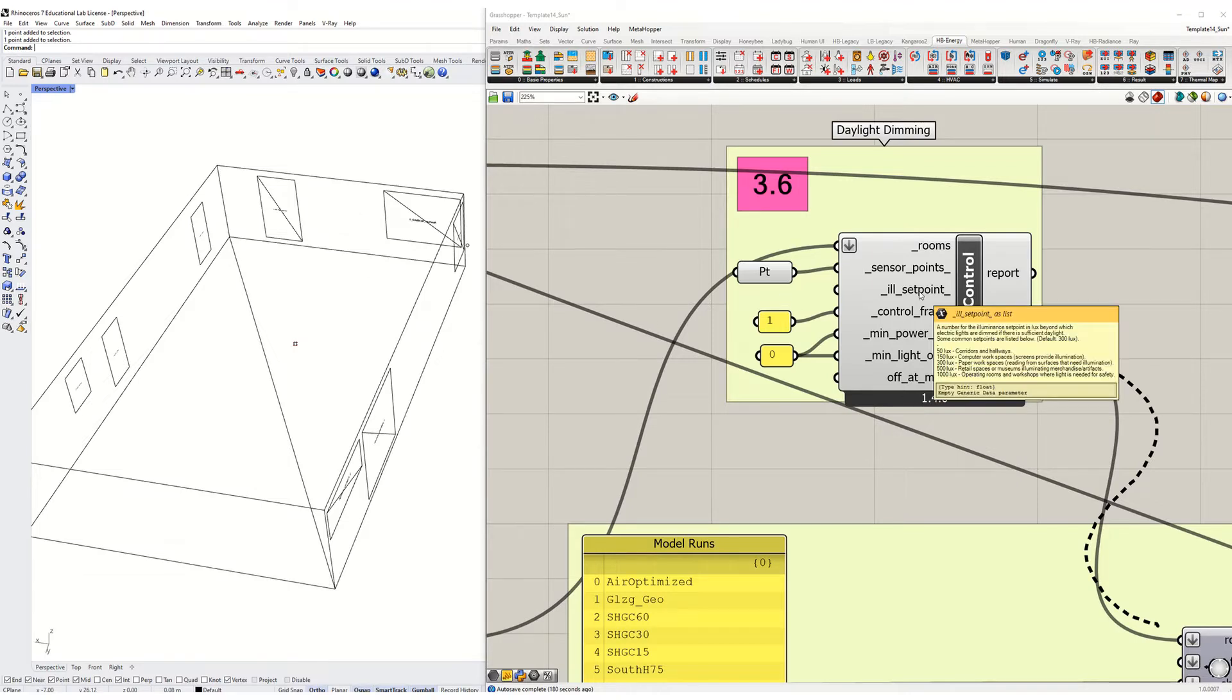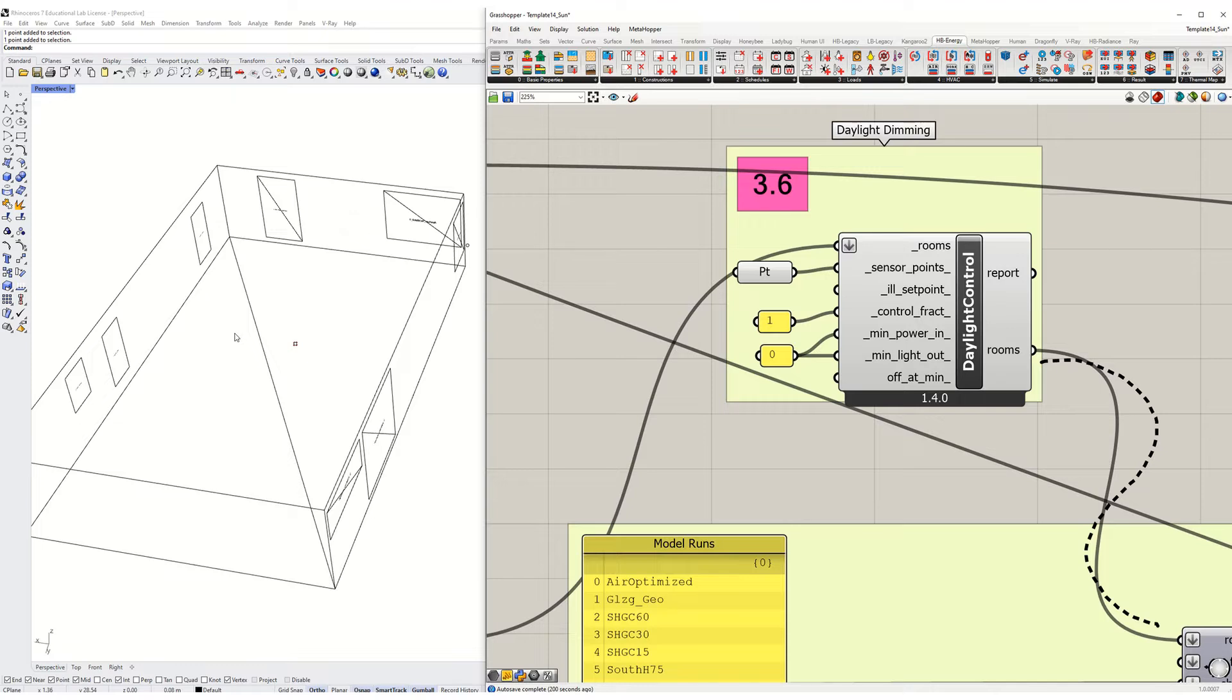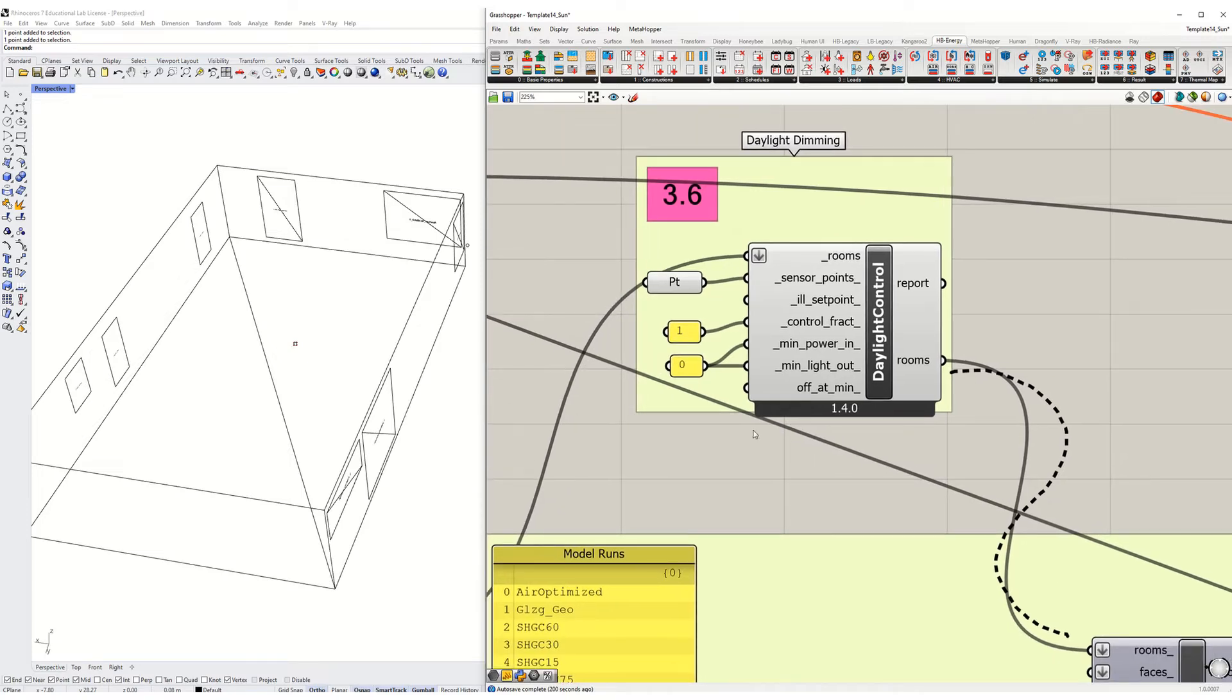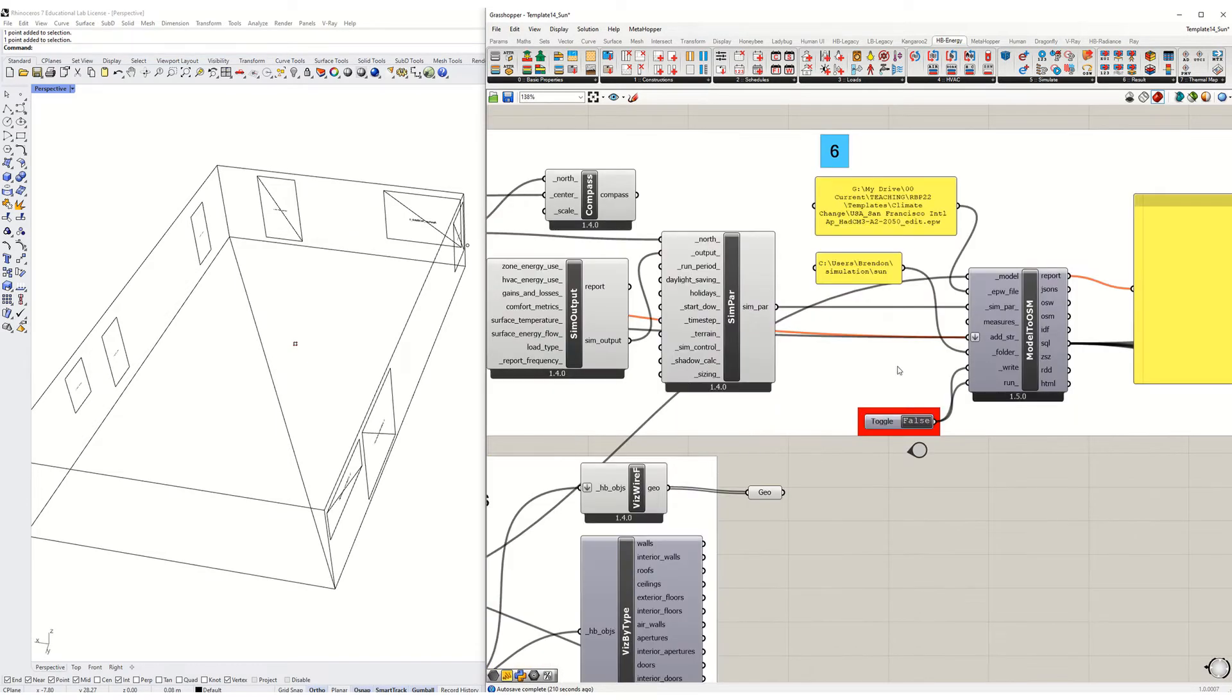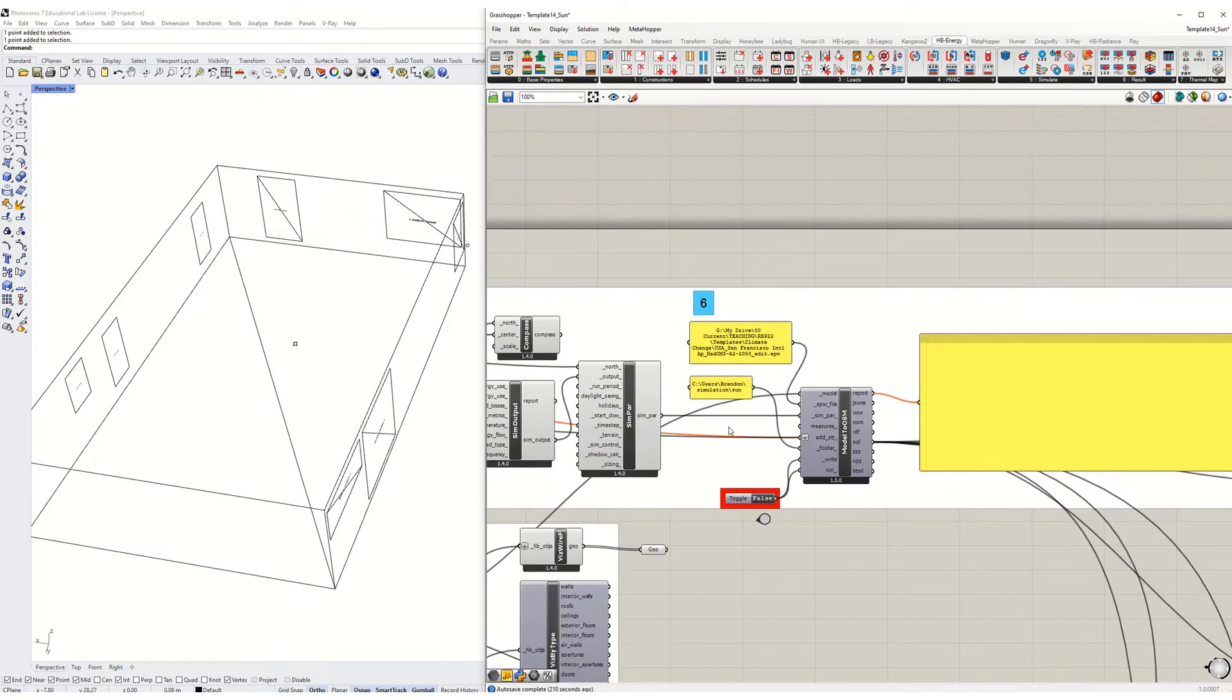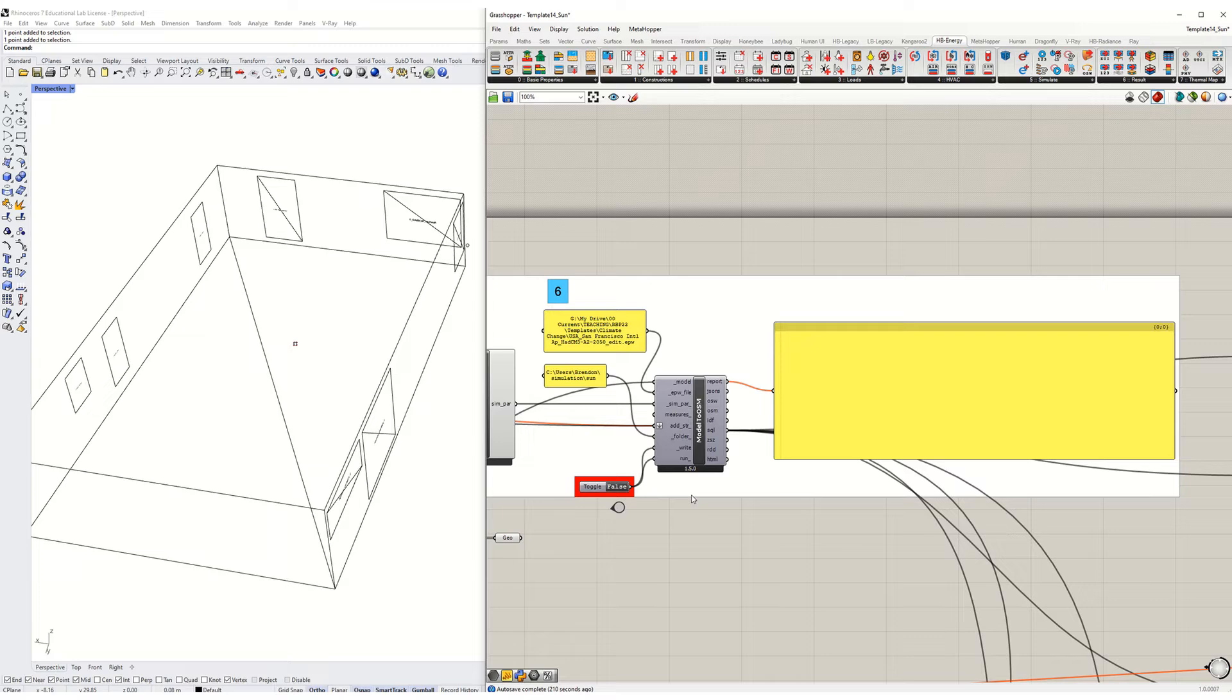The illumination set point is by default set at 300 lux. I'm just going to keep it there for the sake of argument. We can talk about this in class. And then the control fraction is 100% or 1, meaning that 100% of the electric lights in the zone will dim with daylight. Minimum power in and out is going to be set to zero and we should be good to go. So run this and hopefully you'll see a difference in the amount of electric light that your zone uses.